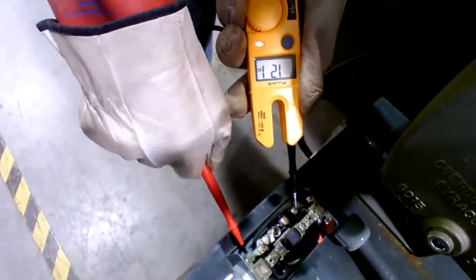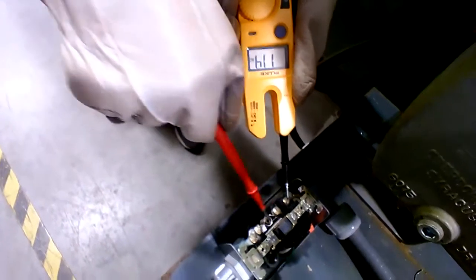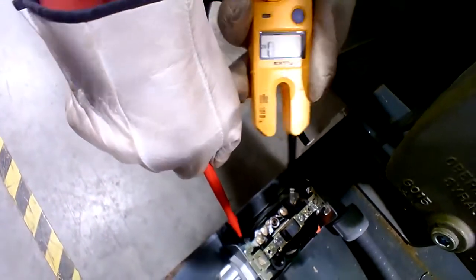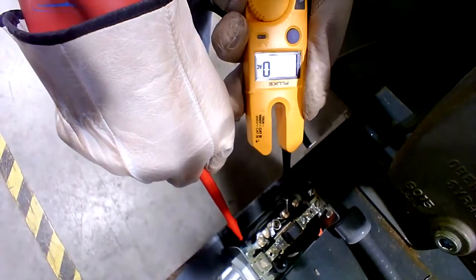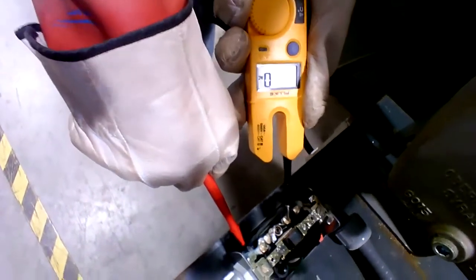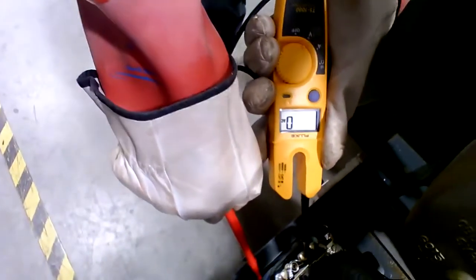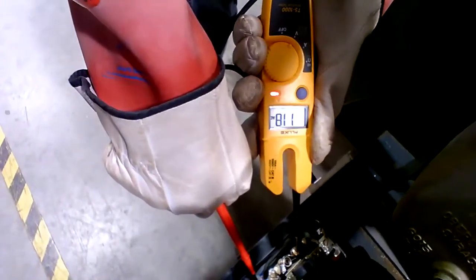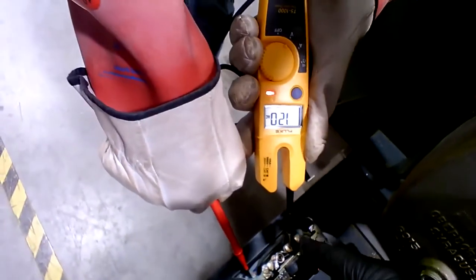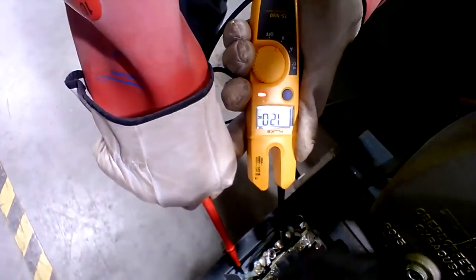Like you got it there. Let's put you right here. So he's checking going into the switch, that's fine. That's checking away from the switch. That's the ground, that's the ground. Now move the probe over. That's away from the switch. And that's not hot, right? It is, and it's like cut it on. You see it cut on, then you can see it go on, like that, just take it. Now you can check it leaving the overload. Move over one more place.